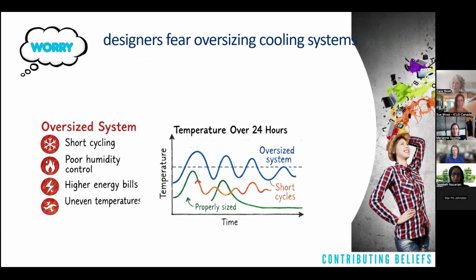So it's important when I'm talking about this to think about each individual system independently. Our in-suite terminals actually have to be right sized, sort of not too big, not too small, like a nice Goldilocks version that's still going to strip humidity out in most days, but then when running 24/7 is going to be able to provide temperature control on those hot and humid days. And then add our makeup air units, where we're pulling a ton of humidity out of 100% outdoor air, to be really aggressive in how much capacity we put in our coils.